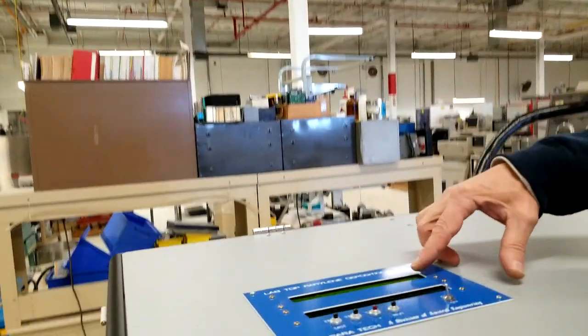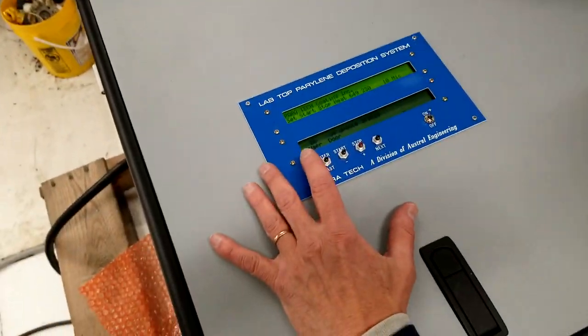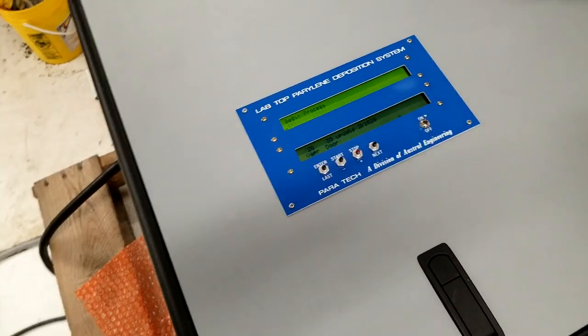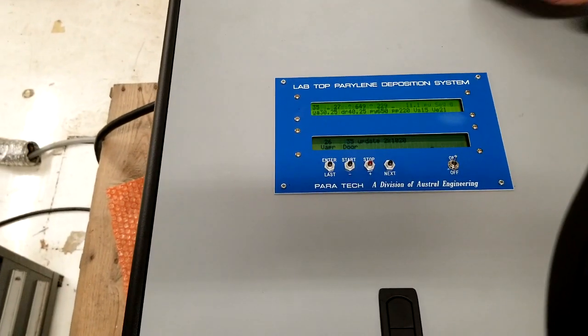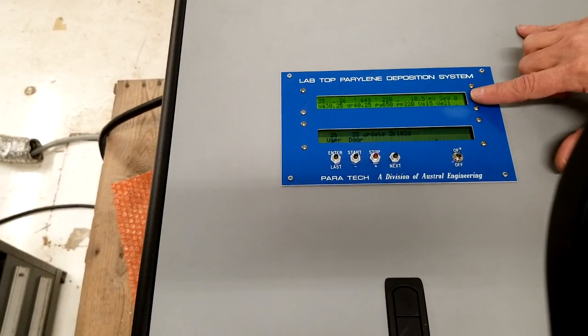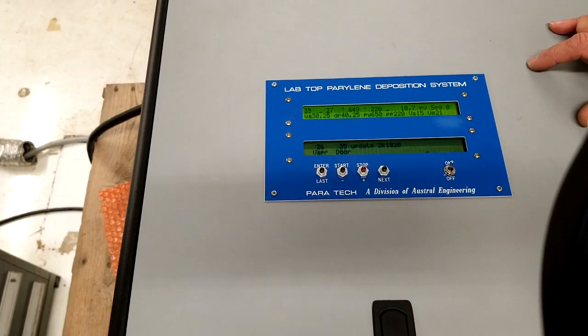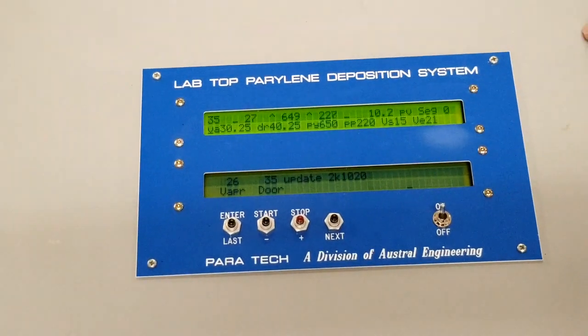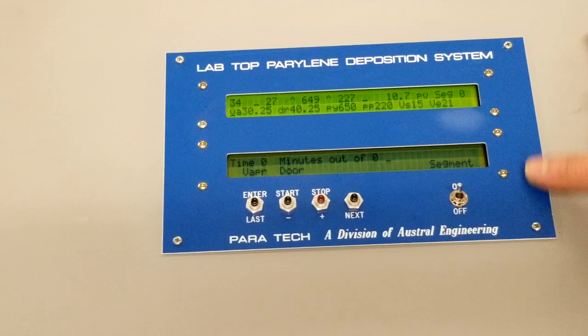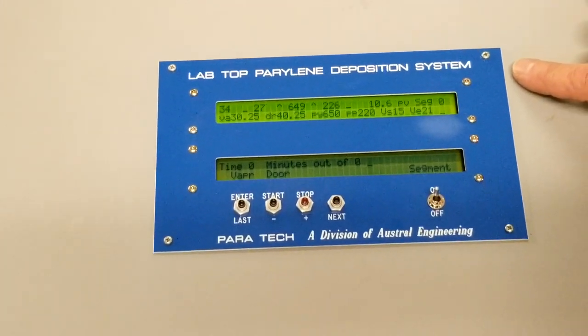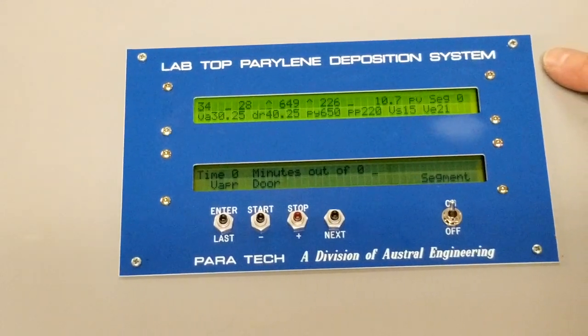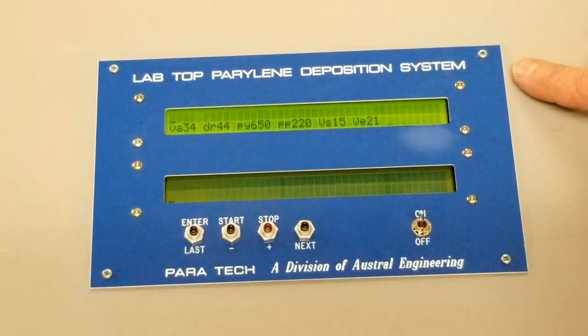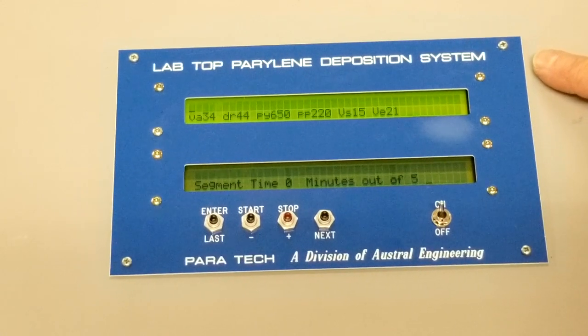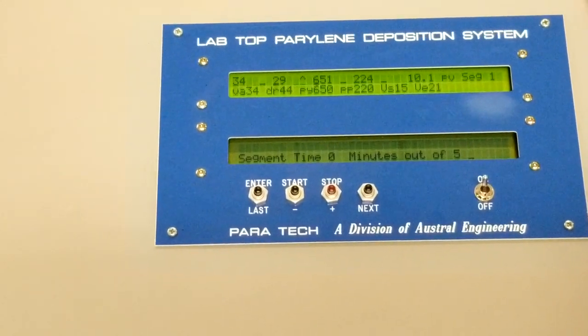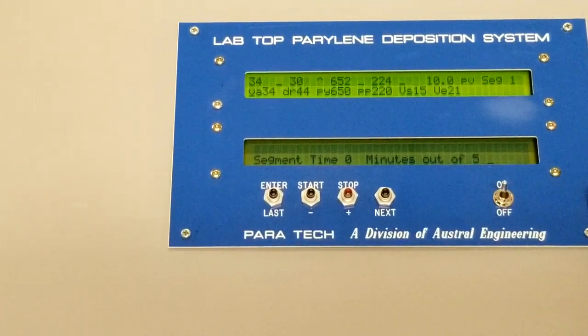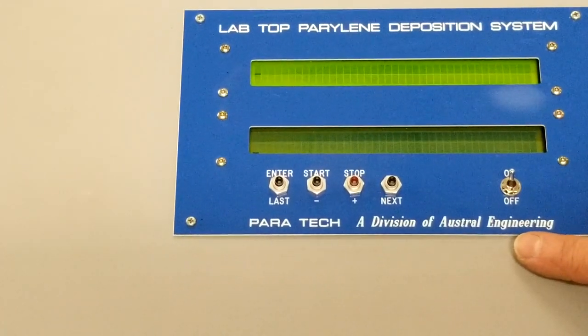So as you can see, we're at 12. We're at 11 microns right now, so I'll go ahead and hit start. And you'll see that the process will begin. Now, it's just showing you what the temperatures are. We're in segment 0. It should start up into segment 1. It checks for the vacuum pressure. And you see we're at 10, so it's below the 15 that we put in our recipe, and now segment 1 is starting.